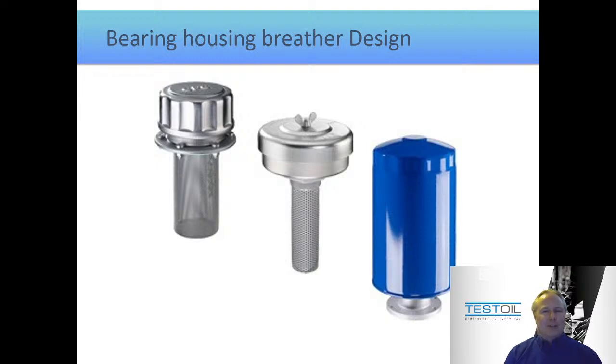Because if we have high amounts of dirt and dust getting in there, we probably don't have a great breather on here. So right away, if we found that we were using one of the lesser quality breathers, we might consider upgrading to a higher quality breather. Or if we're only using the mid quality, we'd consider upgrading to the highest quality. Right? That could be what it is.